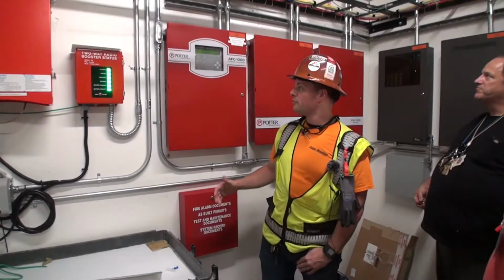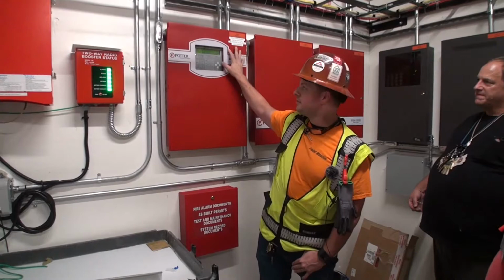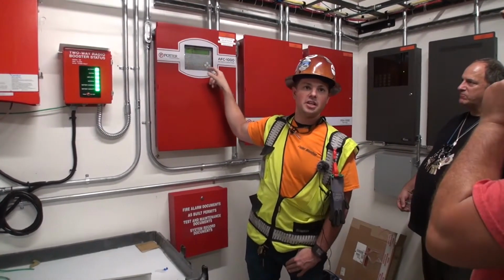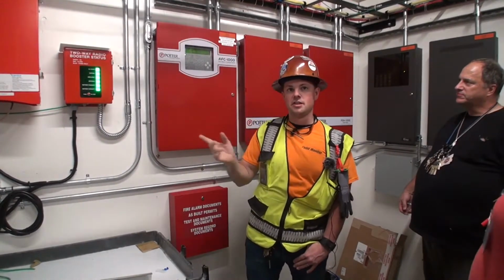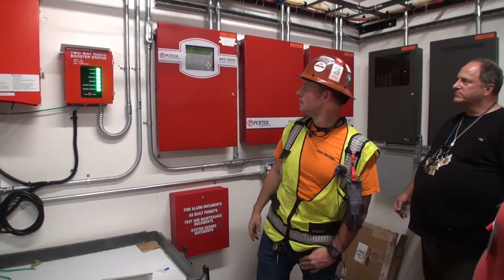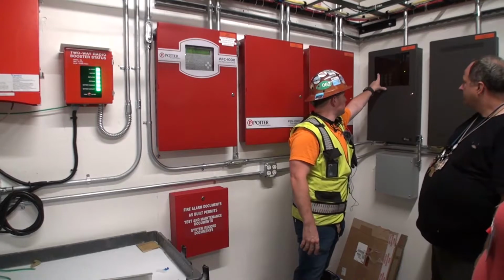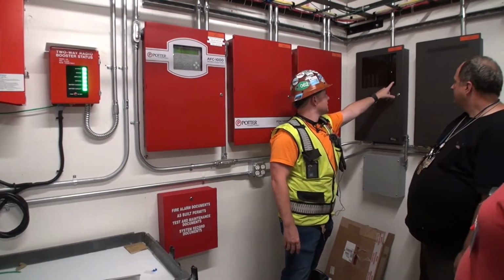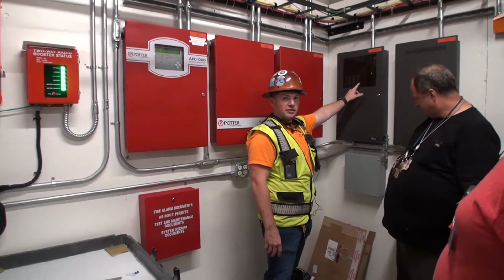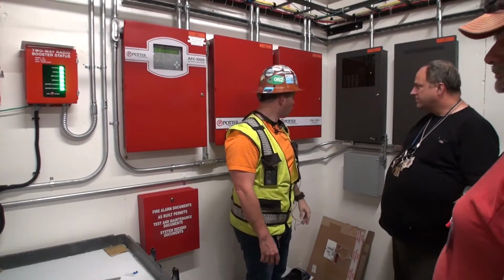This is the main fire panel room where the main fire panel lives. As I was saying before, this annunciator is just a repeat of the annunciator in the main office and in the arts building. This is the main voice evac panel where you can page specific zones. It has a microphone in it as well, and you can also activate a main all call.